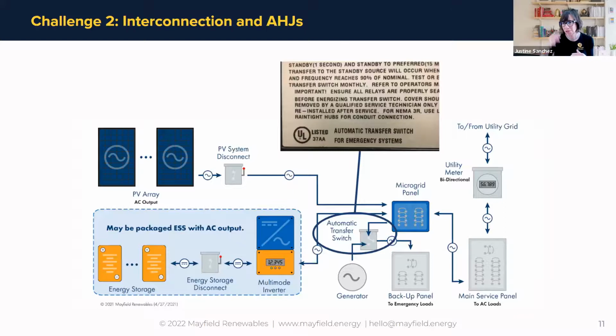So if you start diving into microgrids for resiliency for commercial facilities, you might run into an emergency panel and have to comply with the rules of Article 700. In this case, we did. The AHJ said this was already set up with an existing 150 kW diesel generator, already wired to an automatic transfer switch listed for emergency systems. There's a whole separate ATS for an optional standby panel, which has all the other circuits they wanted backed up by the generator as well. They had to keep those separate, so there were 2 ATSs in the system.